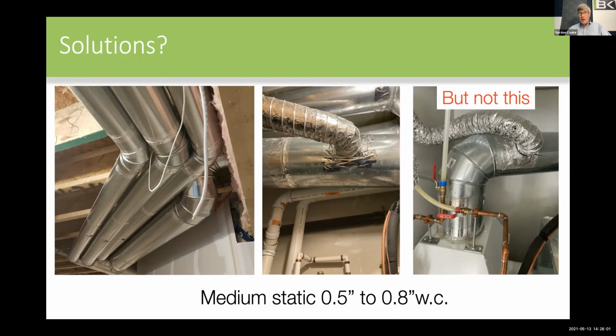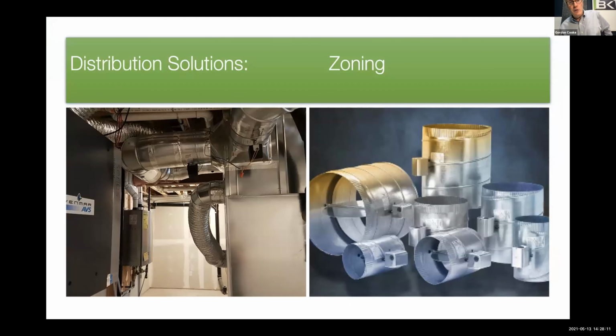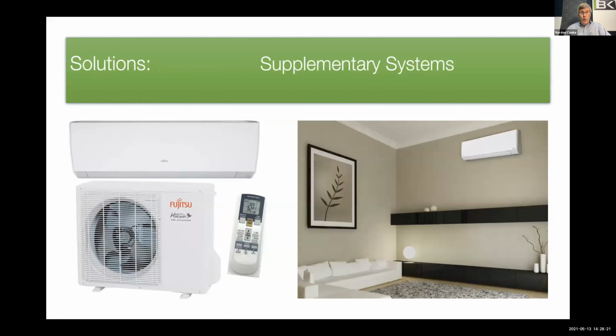But when you're at 1.2 inches of static, guess what? Every one of those elbows leaks. So you need to do a better job of sealing if you're using the higher velocity ducts. And I'm going to say to you, you're probably going to move towards zoning. A room over the garage, the second floor, whatever, probably needs, in high performance houses, you're going to get to zoning. Or you're going to move to supplementary heat pumps.